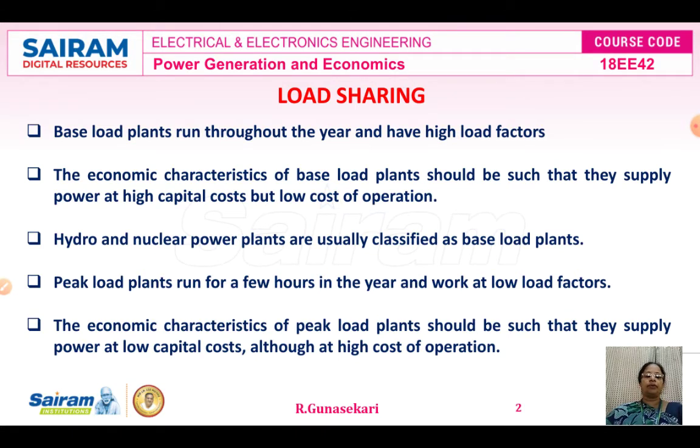The base load power plants, for example thermal power plants and nuclear power plants, are run throughout the year and have a high load factor. Load factor is the ratio of average load to the maximum load. The economic characteristics of a base load power plant should be such that it supplies power at a high capital cost but low operating cost. The hydro and nuclear power plants are usually classified as base load power plants.